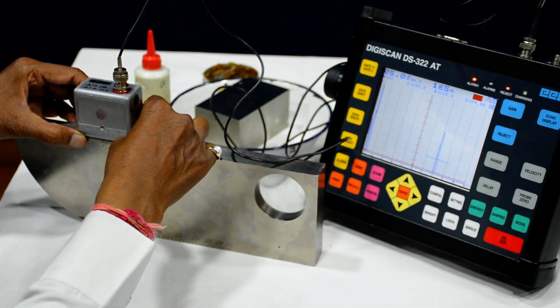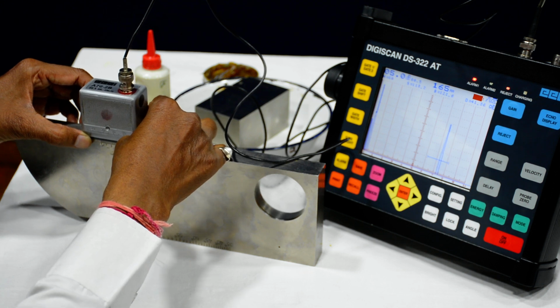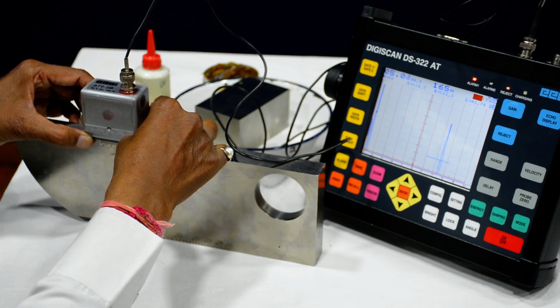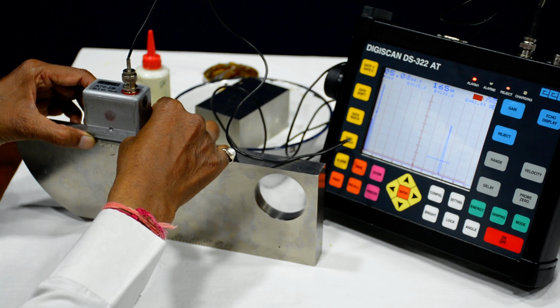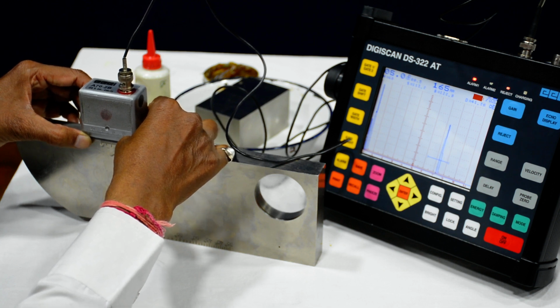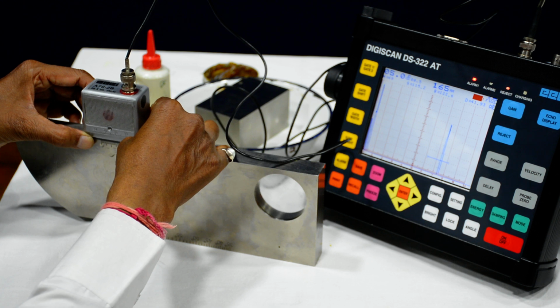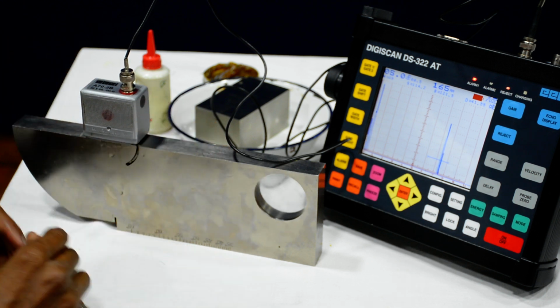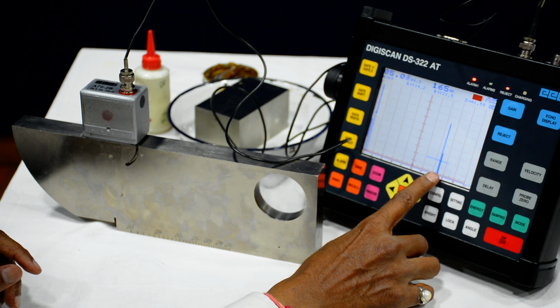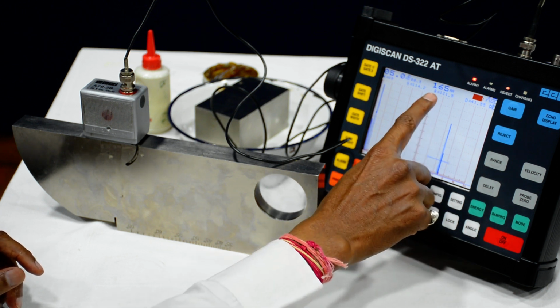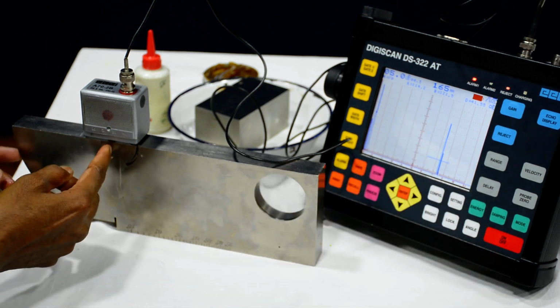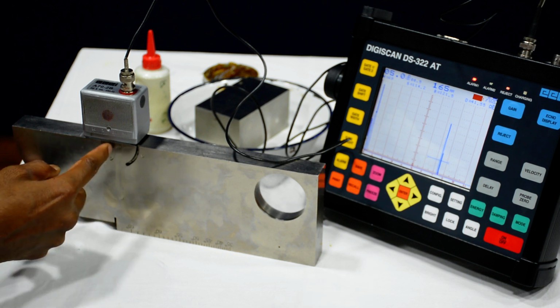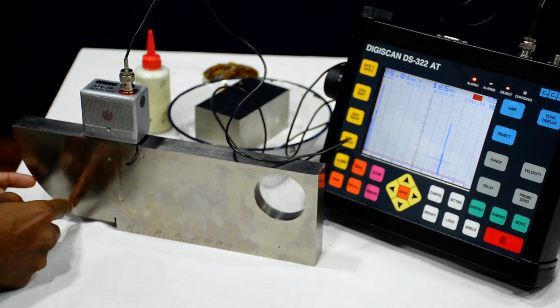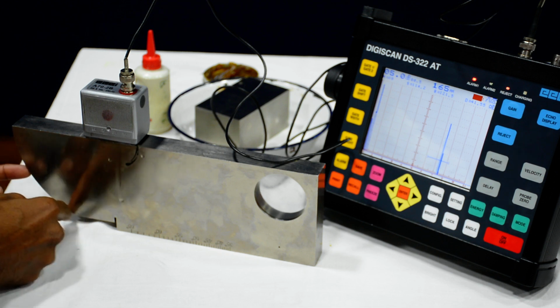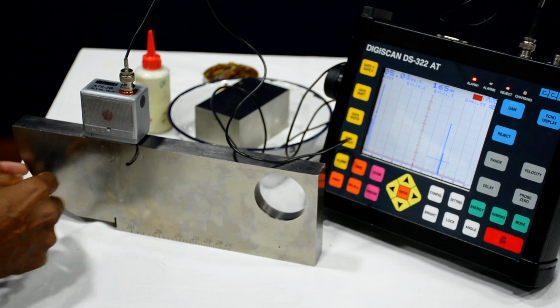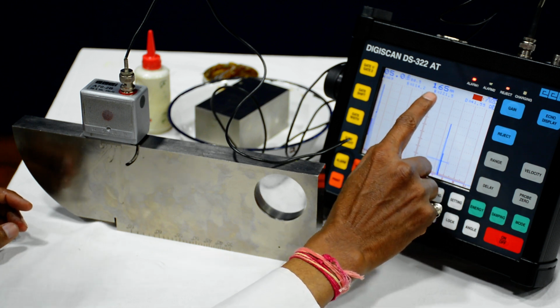Okay, now this is the location. Here this is decreasing, now increasing, decreasing. Here this is the point at this location, height of this echo is maximum. Now we have to see the beam path. This is the beam path. Here this is the beam path, this is the radius. So from this center the radius will be always constant because this is the arc of this center. So we have to make this beam path 100.